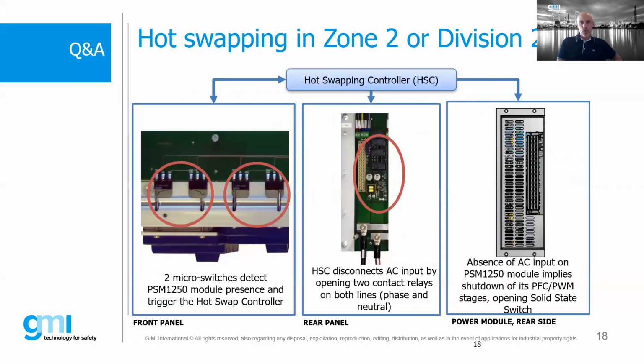Okay, and another point is this one. Another feature that we can offer is hot swapping. Hot swapping in zone 2 or division 2 is assured by micro switches that detect the module presence, and there is the HSC that disconnects the AC input and pre-opens the contact relays. So there is real control, and these are certified devices for hot swapping in hazardous areas.